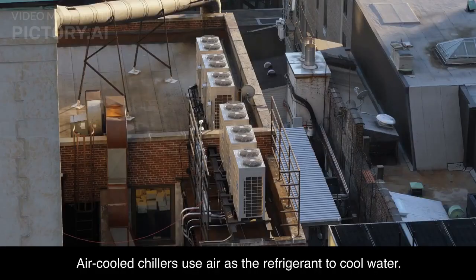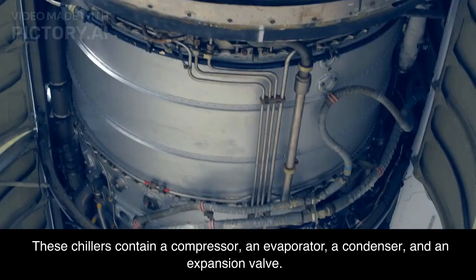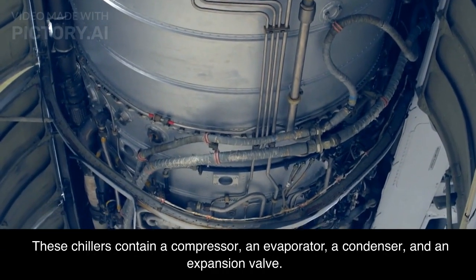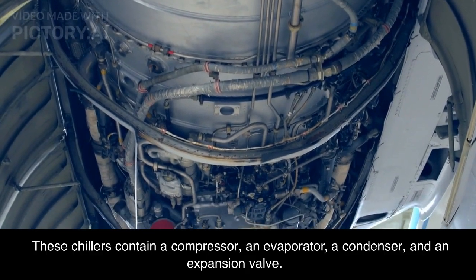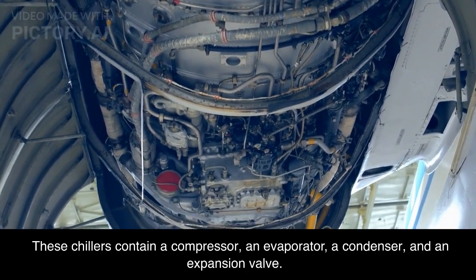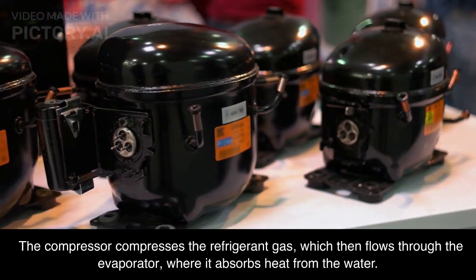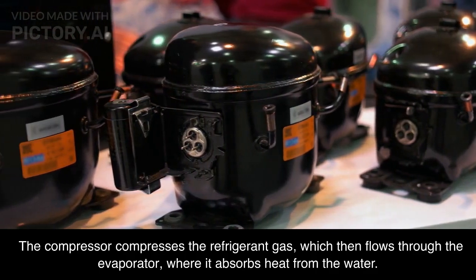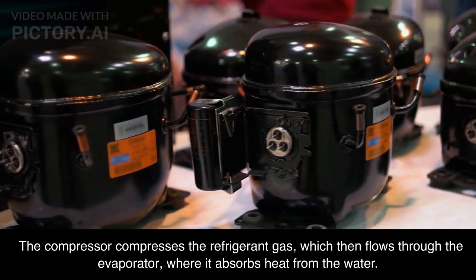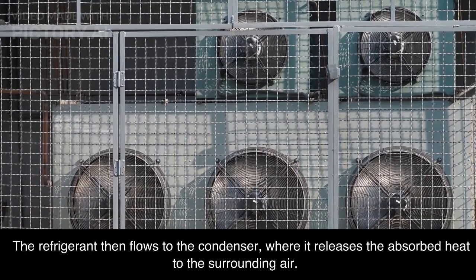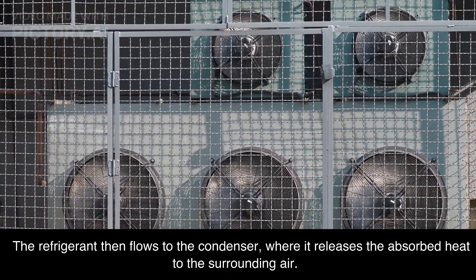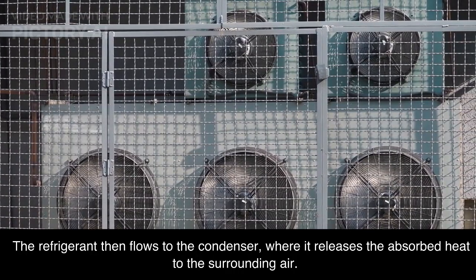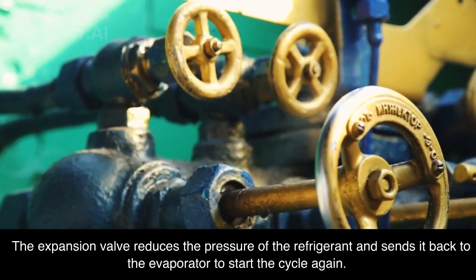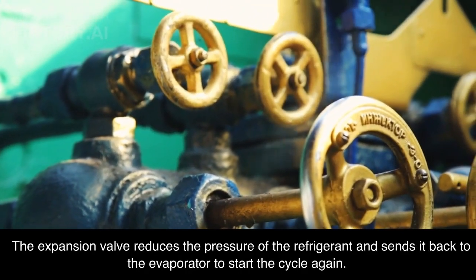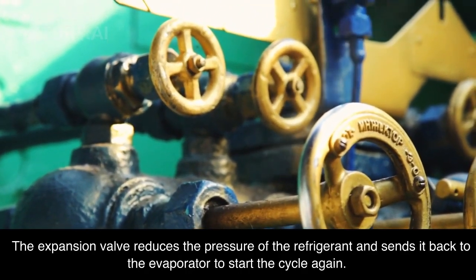Air-cooled chillers use air to remove heat from the water. These chillers contain a compressor, an evaporator, a condenser, and an expansion valve. The compressor compresses the refrigerant gas, which then flows through the evaporator, where it absorbs heat from the water. The refrigerant then flows to the condenser, where it releases the absorbed heat to the surrounding air. The expansion valve reduces the pressure of the refrigerant and sends it back to the evaporator to start the cycle again.